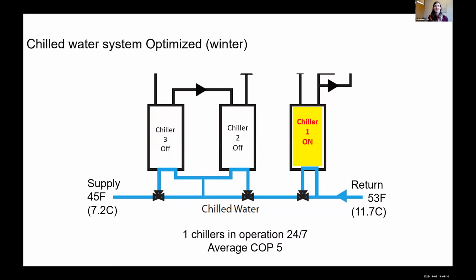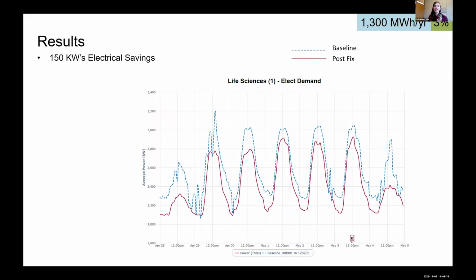And for those of you that know chillers, they do like to be loaded up in terms of efficiency. The results were roughly 150 kilowatts of electrical savings. Because of the magnitude of this building, small changes in programming or operation have huge savings in energy reduction. And that is one of the things when you're looking at energy conservation, is to really try to focus on the larger systems and the larger buildings, because you get a lot more bang for your buck. You need to think about, what am I going to spend my time on? You're going to spend your time on the larger systems.